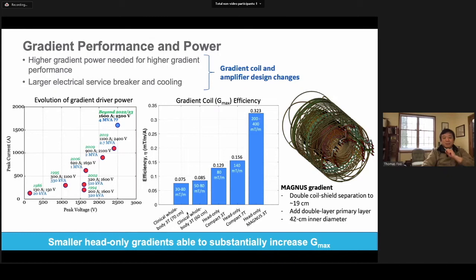But the maximum gradient amplitude that can be achieved is also limited by the efficiency of the gradient coil. Clinical whole body gradient coils have about a 0.08 millitesla per meter per amp efficiency, which means that with maybe 1 to 3 MVA drivers, they can achieve a maximum of somewhere between 80 and 100 millitesla per meter. Dedicated head-only systems, because of the smaller diameter, have increased the efficiency a bit to about 0.13 to 0.16. However, recently we introduced the Magnus gradient system that was able to achieve an efficiency of about 0.3. So with a 1 MVA driver, it can achieve a 200 millitesla per meter maximum gradient amplitude.